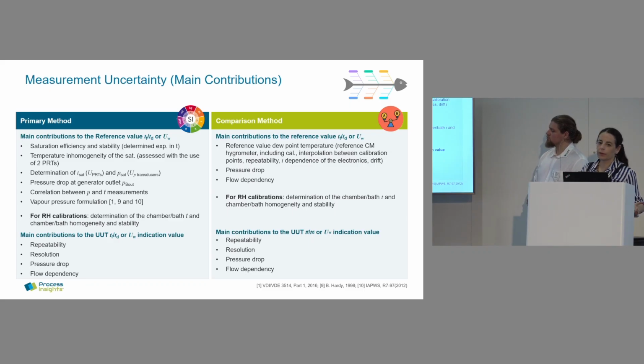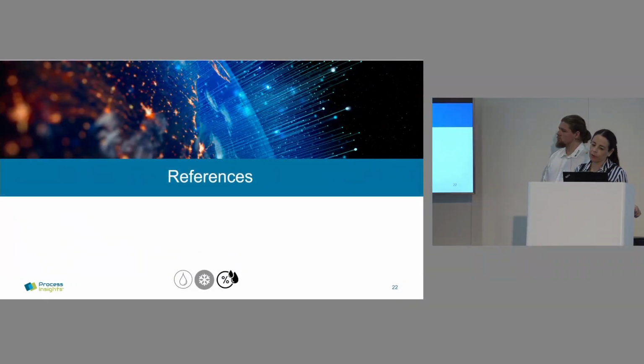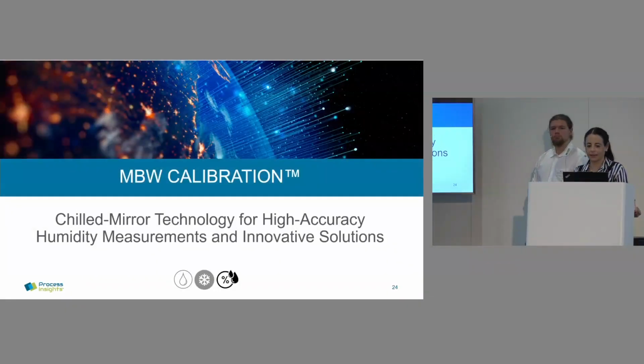When we are doing relative humidity calibration, we need to add also the uncertainty coming from the homogeneity and stability of the bath or the calibration medium. In the comparison method, the main contribution, of course, comes from the reference, pressure drop, and the flow. The same for relative humidity. And from the UUT, the unit under test, the basic ones: repeatability, resolution, pressure drop, and flow dependency. I will leave you the reference, and that's it from my side.